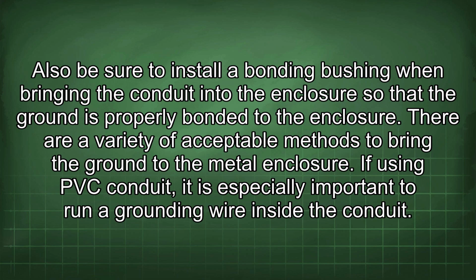Also be sure to install a bonding bushing when bringing the conduit into the enclosure so that the ground is properly bonded to the enclosure. There are a variety of acceptable methods to bring the ground to the metal enclosure. If using PVC conduit, it is especially important to run a grounding wire inside the conduit.